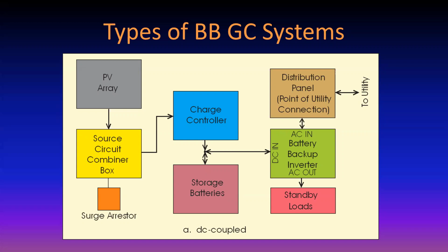It's nice to have a surge arrestor in the system to protect the electronics, because the charge controller has some fancy electronics in it. It has what's called maximum power point tracking. What that does is make sure that the array runs at its maximum power, and we'll see what that implies in a minute. Then the battery backup, well, that has to have storage batteries, and the charge controller is the device that controls when the batteries may have to be shut down. Normally what happens is the batteries fill up, and any leftover electricity then goes to that battery backup inverter, where it's used to power standby loads. If there's any extra left over, it goes back up to the main distribution panel and powers some more loads there. And if there's still some leftover electricity, it goes back out to the utility, as indicated by the double-headed arrow up there; that electricity can either come in or go out. And that's the scheme here with all of those arrows.